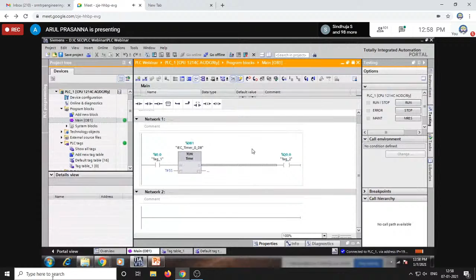I am going online. Since the switch is in on condition, it is directly giving output. Now, the on-delay timer will provide a delay of 5 seconds, and only then will it get the output connected to the input. I am turning on the input, so it will run for 5 seconds. See, the accumulator value is running for 5 seconds. After 5 seconds, the timer will turn on the output Q0.0.